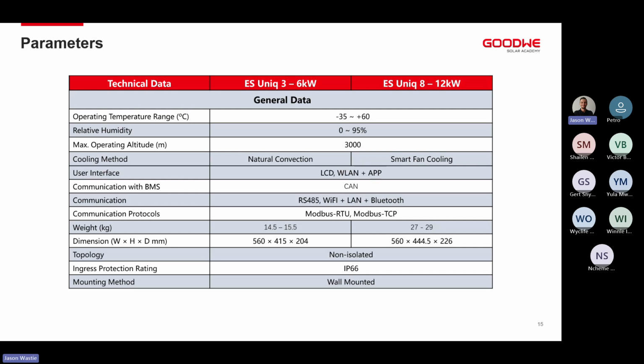On the 3.6, 5, and 6 kilowatt units, the cooling method is natural convection, meaning there is no forced air cooling. There are no smart fans or anything like that on the inverter. It just has a large heat sink on the back of it and cools that way. So it's very close to silent. It runs at 30 decibels when in full production.